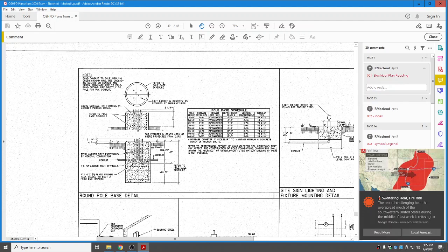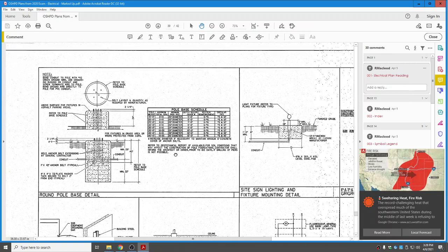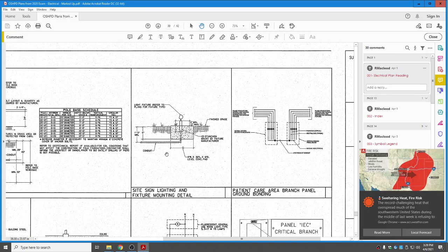Talk about the height of the pole. The minimum pier size would be our diameter, our depth below grade that needs to go, vertical rebar and circular ties there in that concrete. And it gives us some details about how to set the light pole on top of the pedestal, 24 inches minimum, as you can see here, above the typical ground elevation.